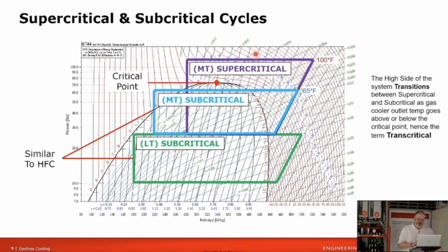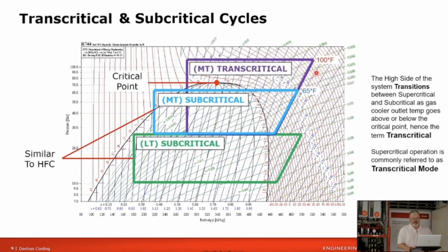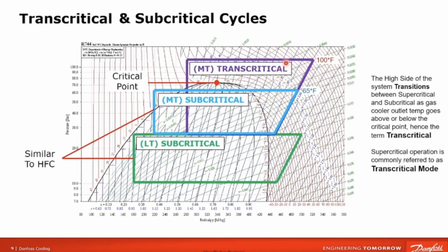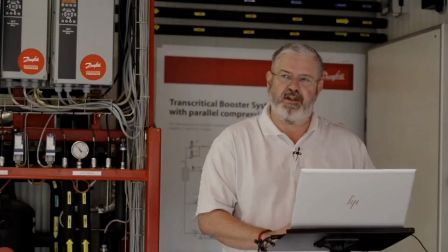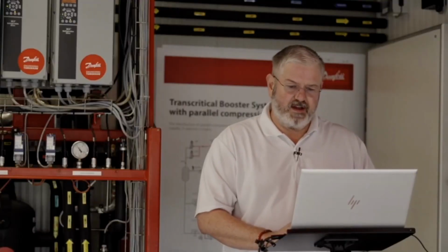And then in the lower ambient, you'll see we're below that critical point. So the system transitions between these two, and most people will call it transcritical when you're in the supercritical region. And that transition from supercritical region here to subcritical region here is where that term transcritical comes from. But most people will refer to the system operating above the critical point of 87. They'll just call it in transcritical mode. That's pretty commonly used across the industry.